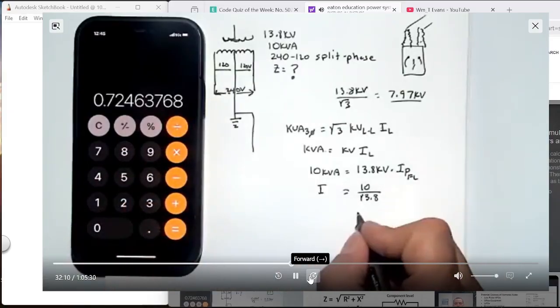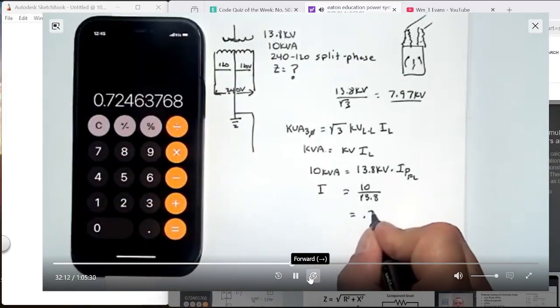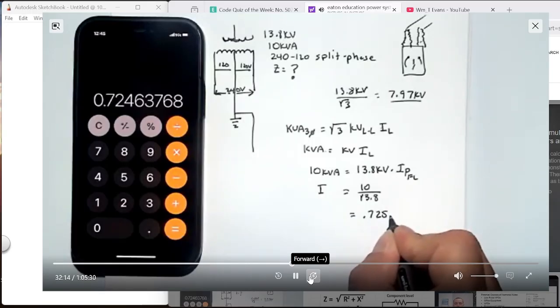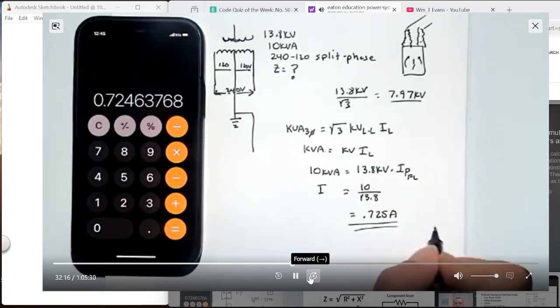And really right away we can see that's less than 1 amp, so 0.725 amps. That's what's kind of cool if you think about it. They could use almost like an Ethernet cable to feed your house. It's very, very low gauge wire, but that's why they can use like a 10 or 12 gauge wire uninsulated in the air, just feeding the primary. And you're going to see that wire is small. It doesn't even need to be as big as it is, because you have less than an amp on the primary.